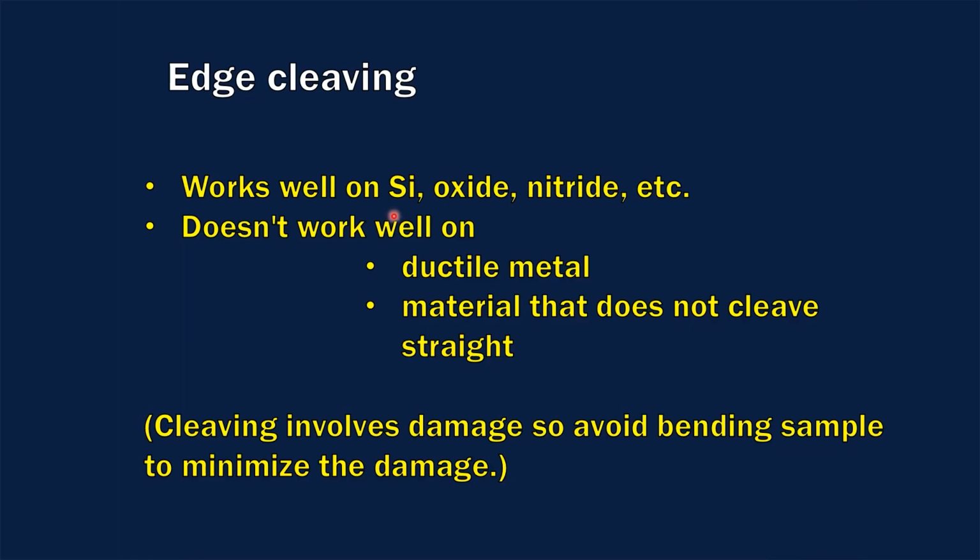In summary, edge cleaving works well on silicon, oxide, and nitride, but may not work well if the substrate or film is ductile metal, or if the material does not cleave straight, or if cleaving involves damage to either the substrate or film. Speaking of damage, a common mistake I have seen from users was trying to break the sample by bending. This actually will introduce more damage to the sample, so please try to avoid bending to minimize damage when cleaving the sample.